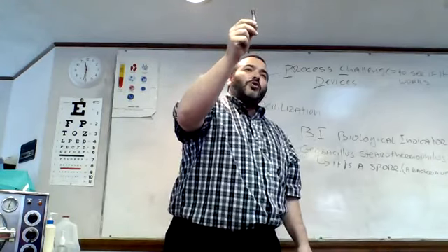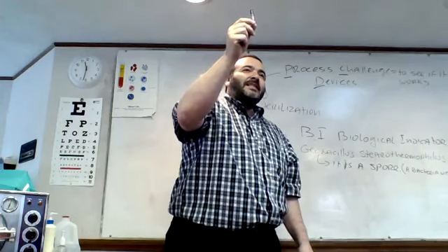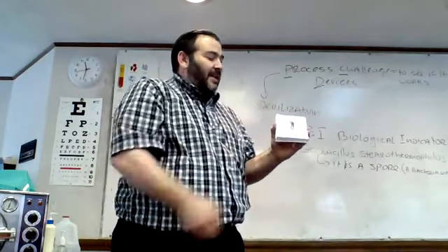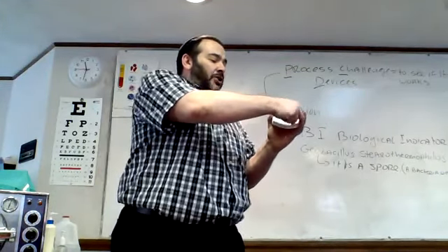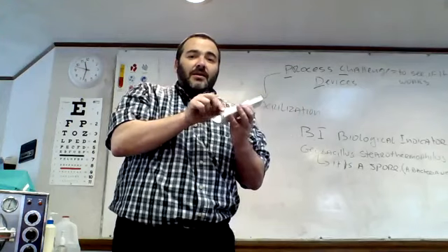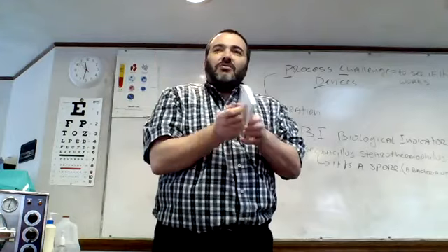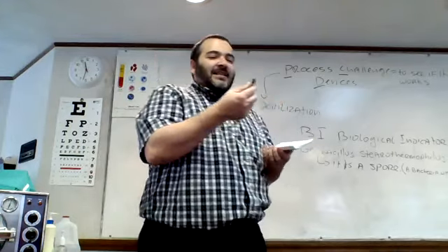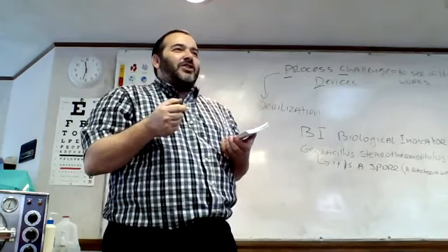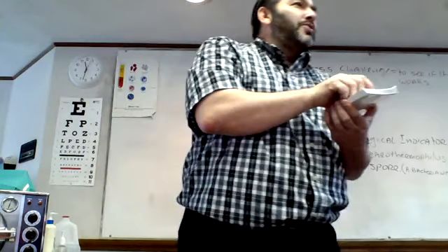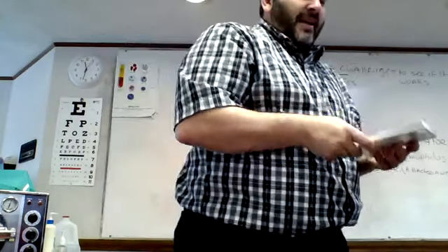So inside this test tube is that bacteria, that spore that we're supposed to kill. It's inside these packages here, right? It lives right there, and it kind of mimics the package. So these 3x5 cards allow the steam to kind of penetrate in there. This makes it more difficult. I could just throw this in the sterilizer and let it sterilize, but no. We want to challenge it to make it as real as possible, for these things to tell us the real truth. We need to make it as hard as possible.